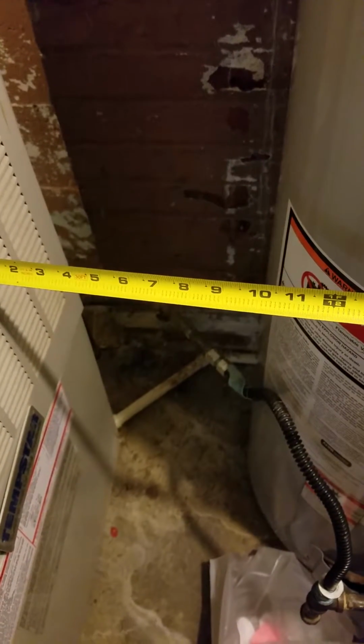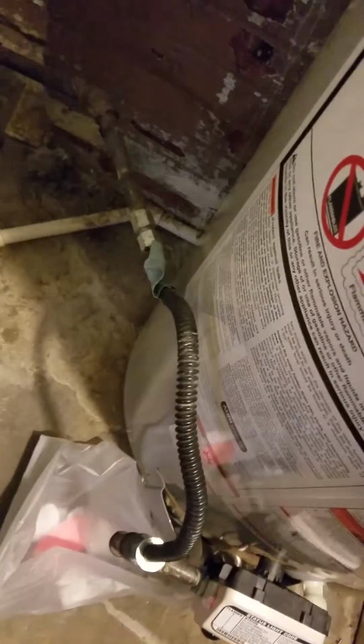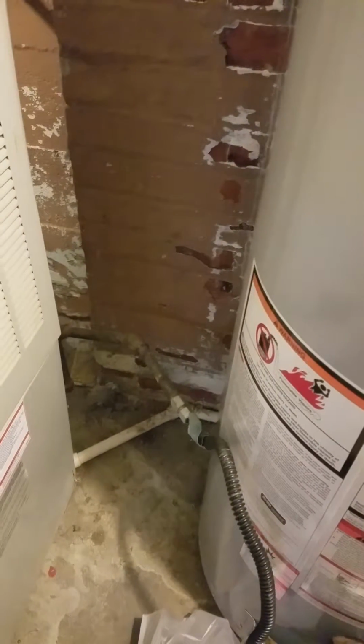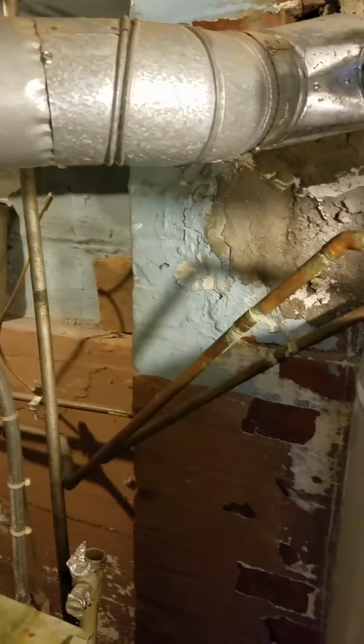Okay, so if you look, there's your flex valve, gas line coming right across there up against the side of the water heater. So we're going to kind of come in at an angle, put it in there, slide it back in there. Got 12 inches from the furnace to the water heater. Then your 4-inch flue to 5-inch single wall right there.